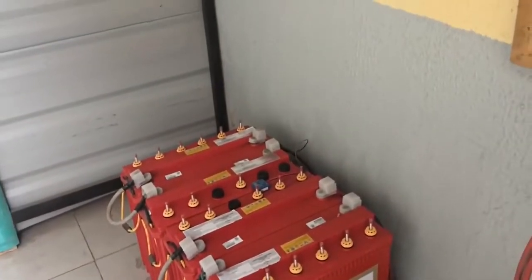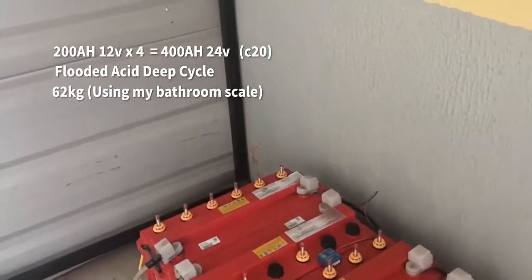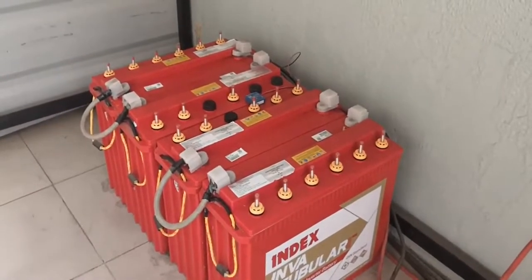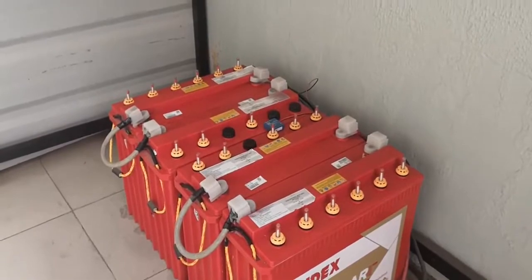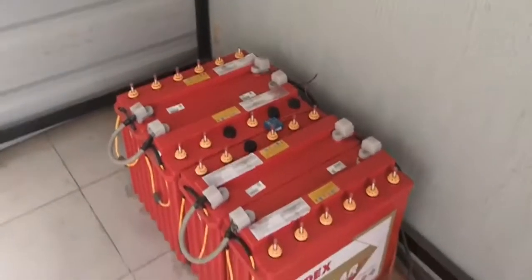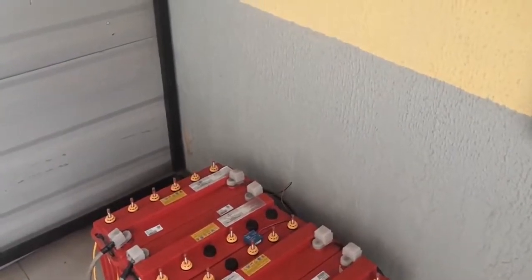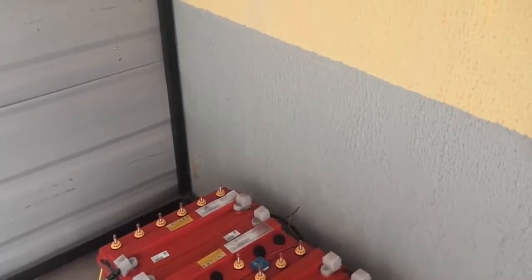For batteries, I have four 12-volt 200 amp-hour flooded acid batteries — these are Index tubular batteries. So far they're performing quite well. I ran a capacity test on them yesterday and I was able to pull 165 amps while discharging them at C10, and the voltage was 23.3 volts when I stopped the capacity test.